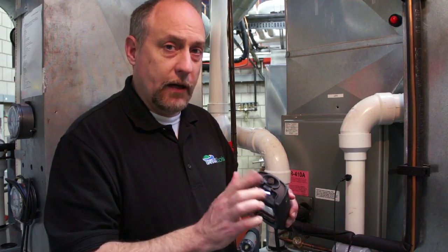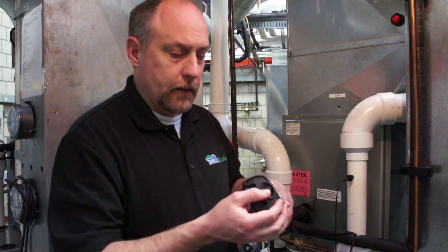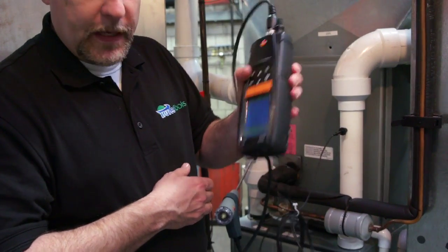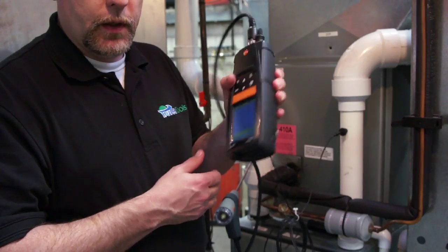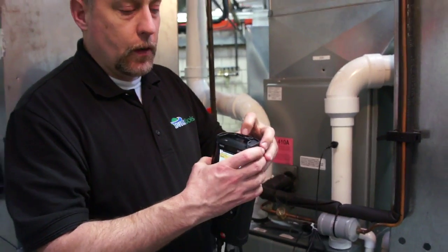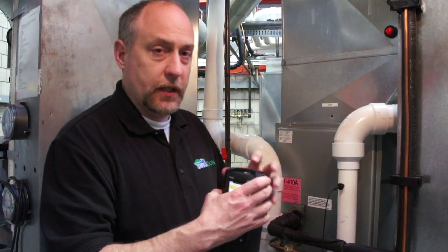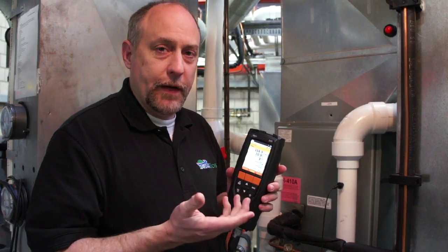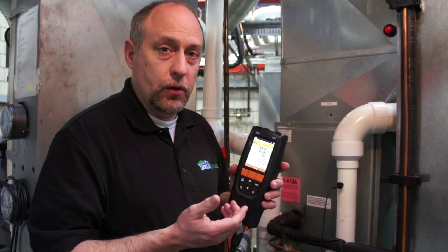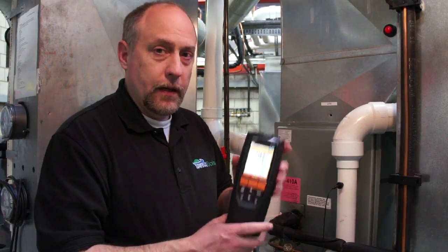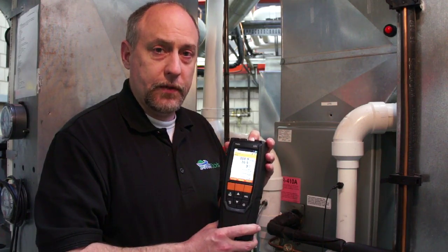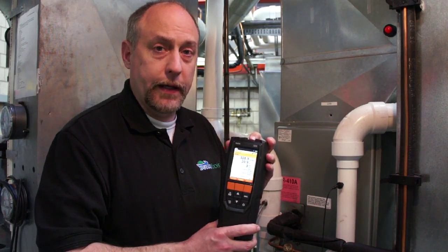The integrated water trap, you empty it by simply pulling up the plug on the top here. You don't want to pull it all the way out, just pull it so it's loose. Turn the instrument upside down, shake it, and you can see the water coming out there. So that's positive proof we're well into the condensing range. And I want to go ahead and close that up by just pushing it on the top again. If you ever have your analyzer reading a high O2 reading and it's not a leak at your probe, make sure that you push down the water trap seal all the way because it can pull in air there.